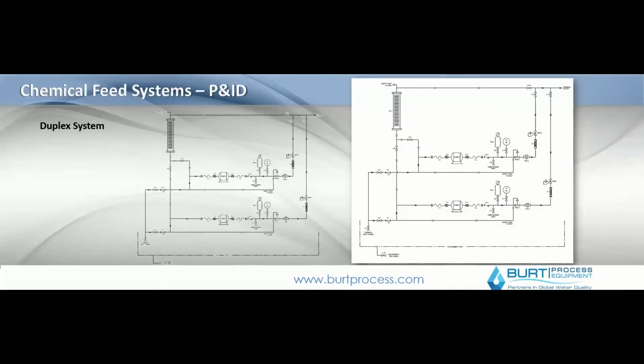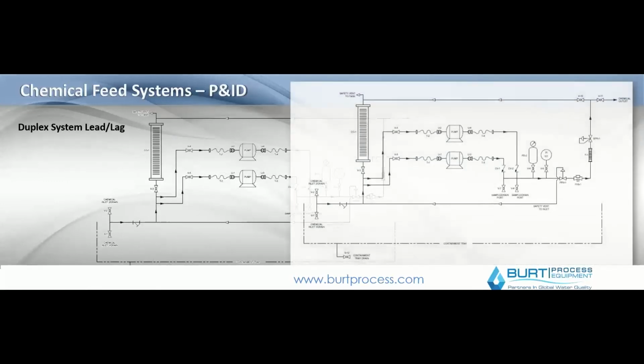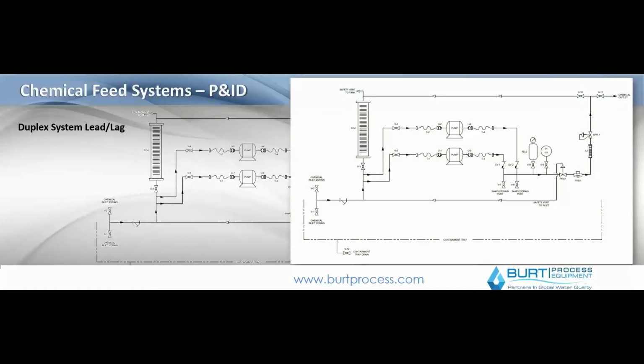Duplex, obviously a lot of chem feed equipment is duplex for that level of redundancy which is involved in the system. Then you only have one calibration column, but basically everything else is duplex, so that if one train is shut down, the other train takes over completely. It allows for continuation of the injection, or the chemical basically being pumped into your system. Duplex lead lag is not as common. In this case, you basically just have two redundant pumps, but you have one shared discharge or one shared suction. This rarely comes up. This is really if you just want to have full redundancy as far as your pump selection is concerned. But it is very similar to a duplex design, and you basically have redundancy in the pumps in that case.